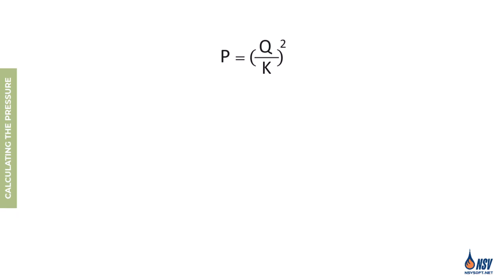In the initial step of hydraulic calculations using standard spray sprinklers, the flow rate of the most remote sprinkler is determined by multiplying the required density by the sprinkler's coverage area. By knowing the flow rate, we can calculate the required pressure by dividing the flow rate by the K factor and squaring the result.